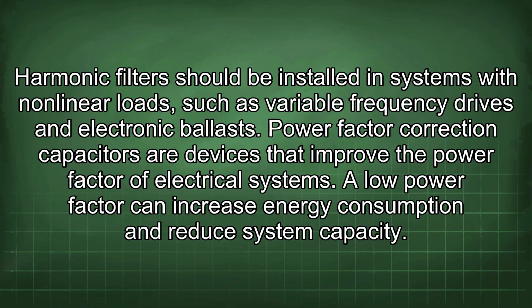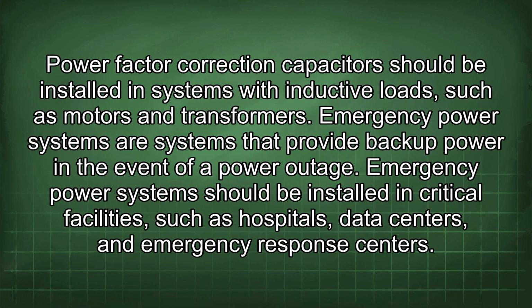Power factor correction capacitors are devices that improve the power factor of electrical systems. A low power factor can increase energy consumption and reduce system capacity. Power factor correction capacitors should be installed in systems with inductive loads such as motors and transformers.